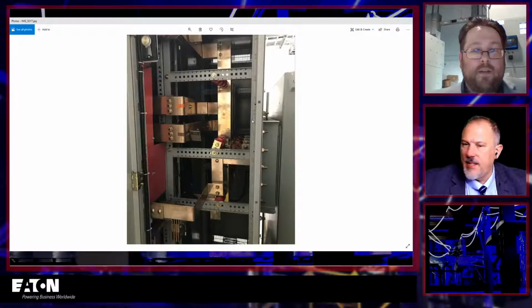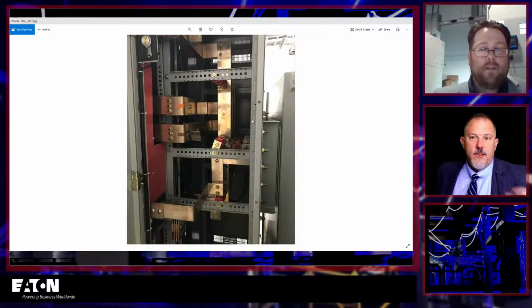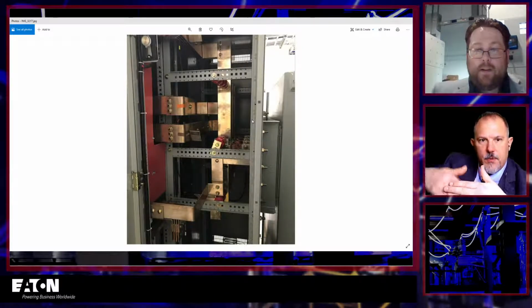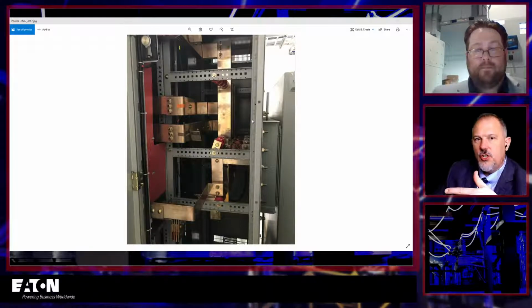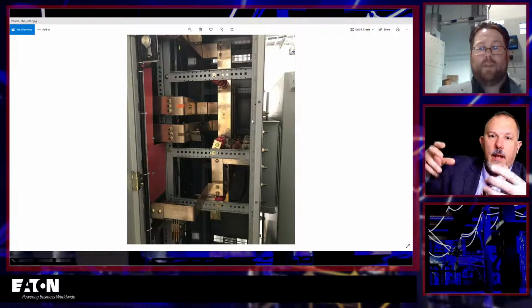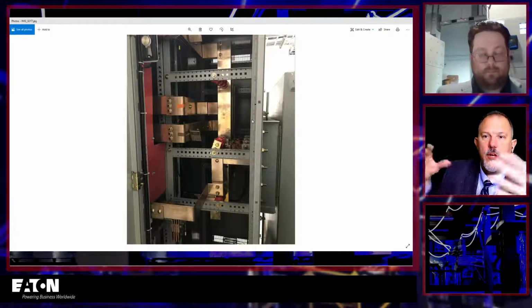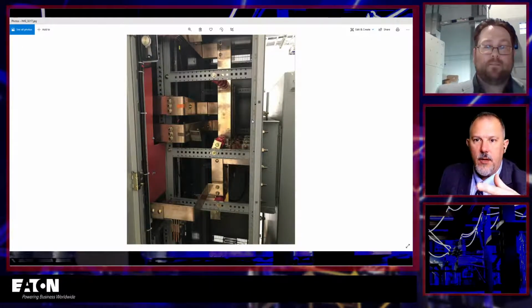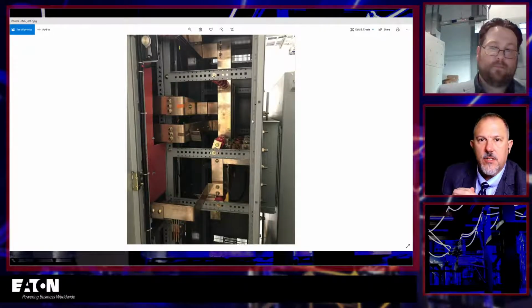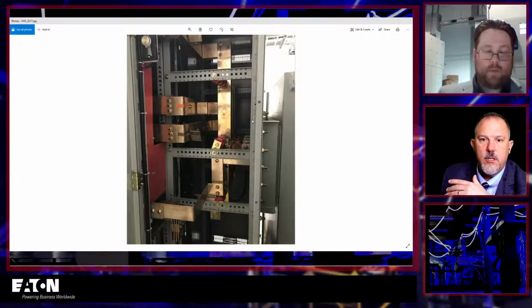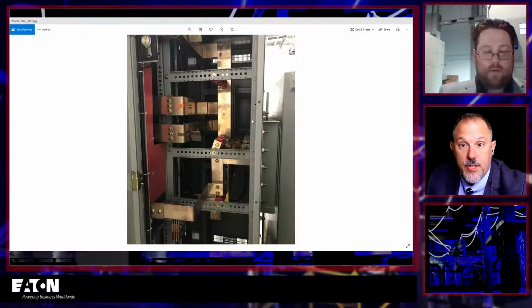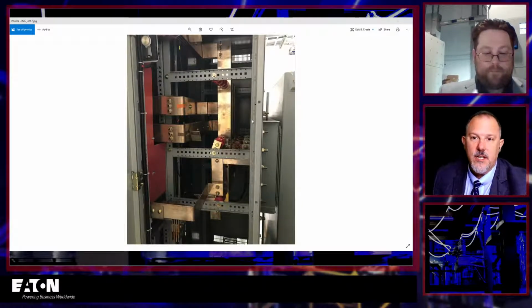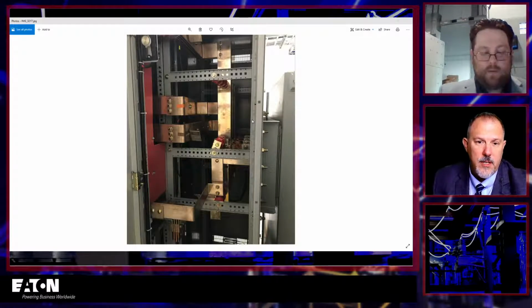So you've got to understand this equipment. You've got to understand everything you just explained about all of the jumpers, what is A, what is B, what is C, because you're going to be clamping and clipping and then trying to isolate things so that, to your point, you're not getting currents flowing out of where you think they're flowing. It can get complicated pretty fast, so it's not left to somebody who doesn't do this routinely. Especially if it's different manufacturers of equipment, things are going to be arranged differently based upon the manufacturer. So you've got to understand the equipment in addition to the technology that you're using to run the tests.